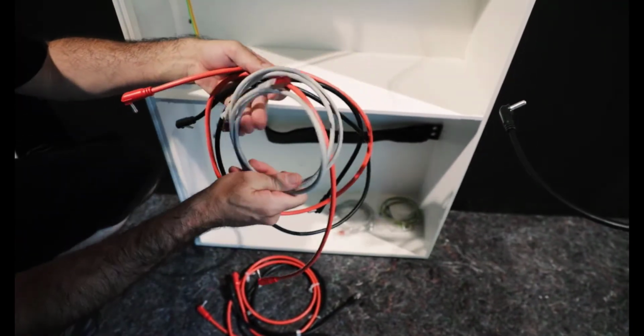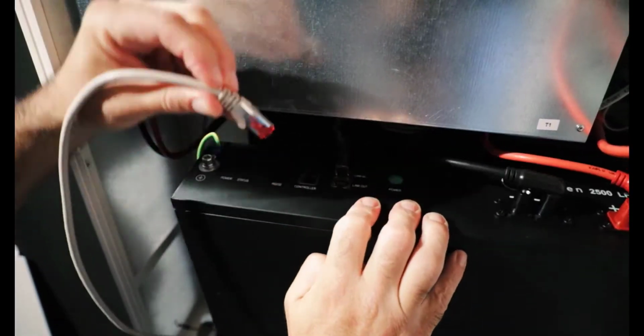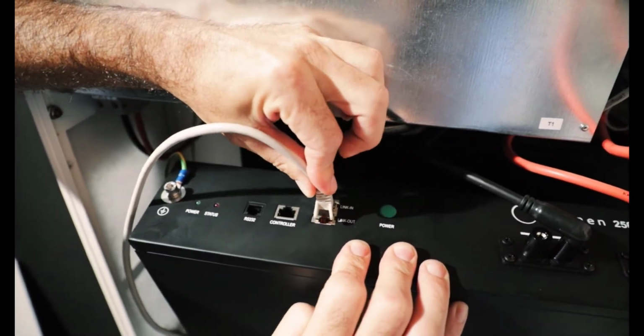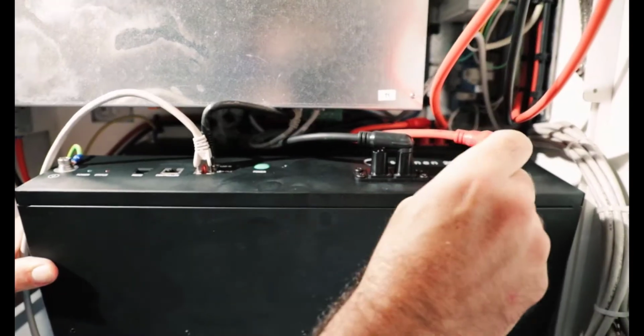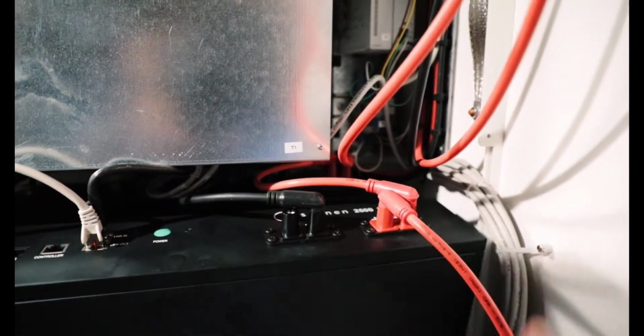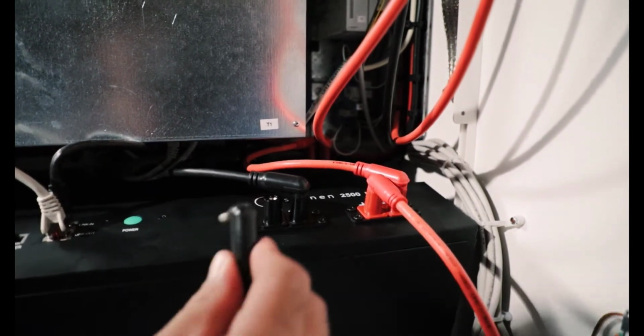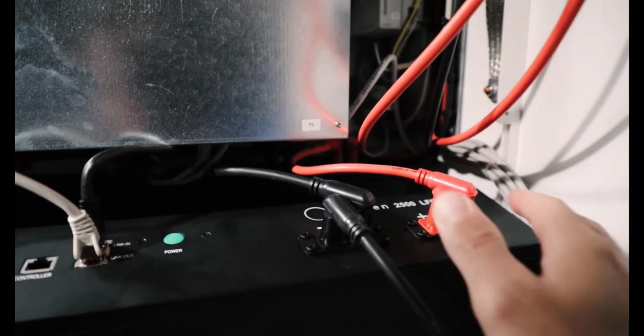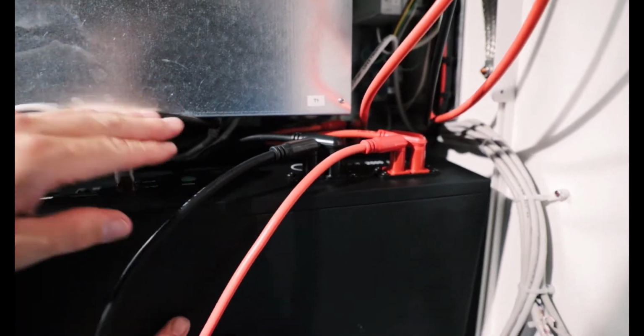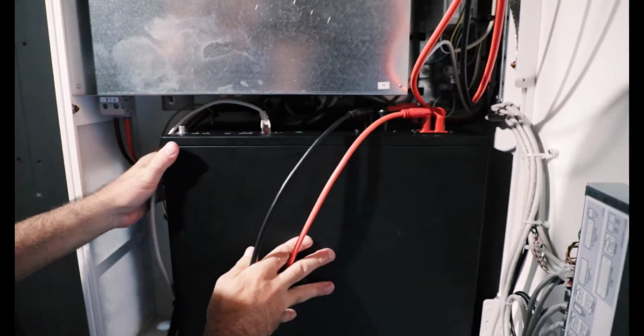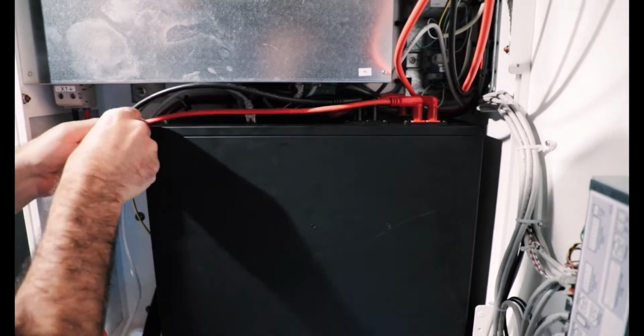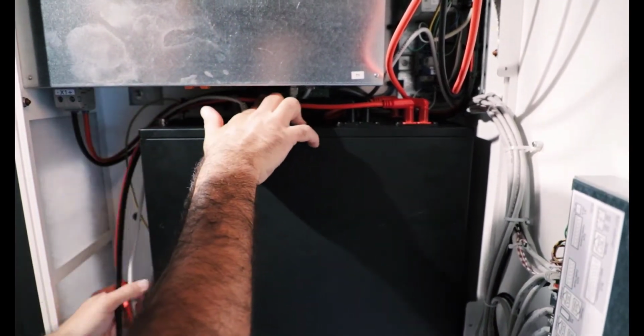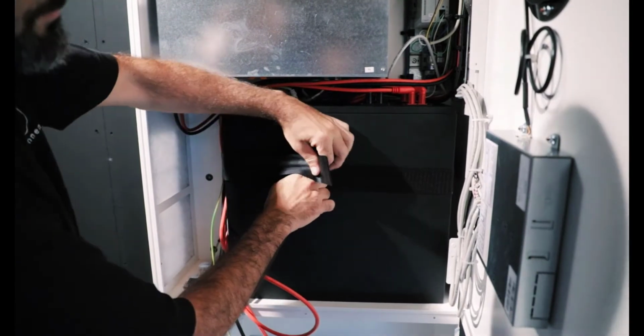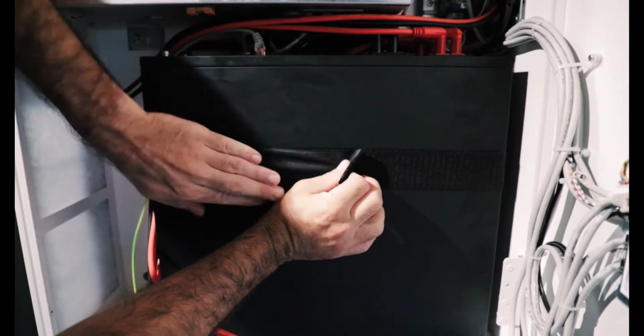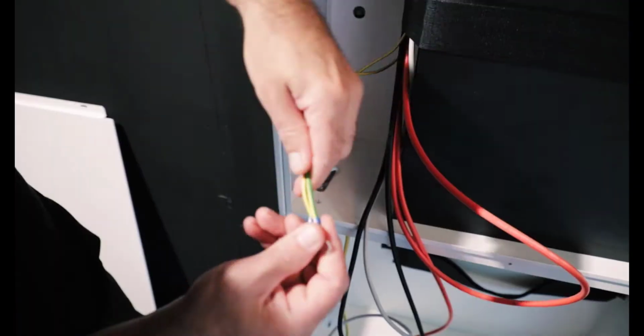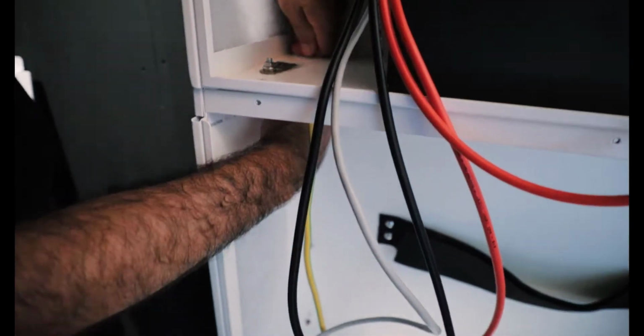Next cables to select are the much longer battery and C-bus cables, because they need to be able to pass from battery module number 2 down through the extension housing to battery number 3. So first thing we do there is put the C-bus cable in, positive and negative. Now what's handy with the Velcro strapping is that we can actually use that also just to hold not only the batteries in place, but also to tidy up all the cables.